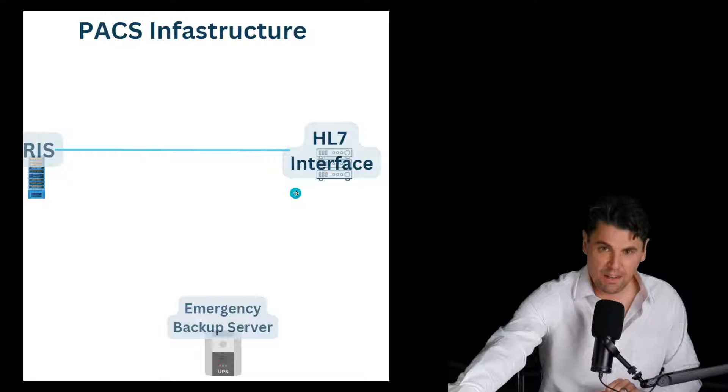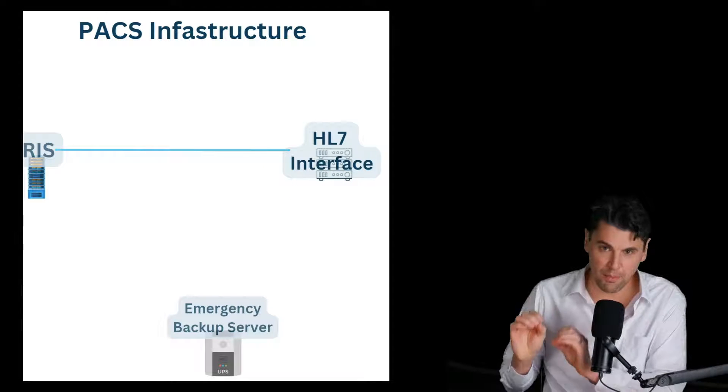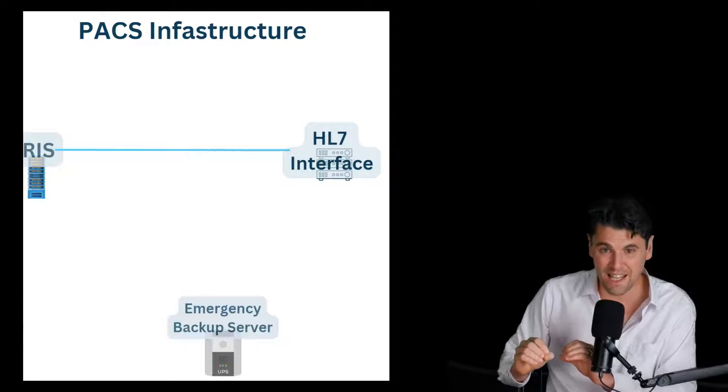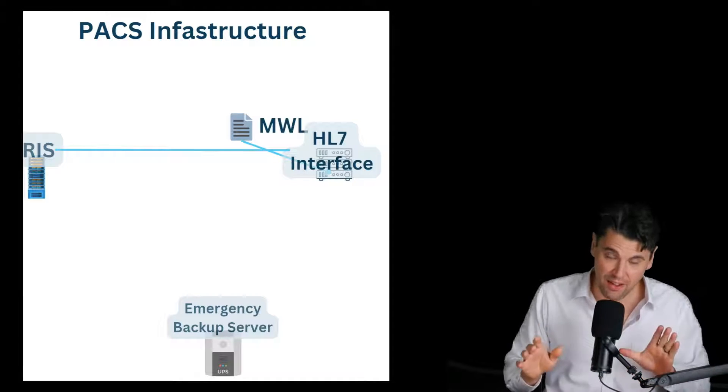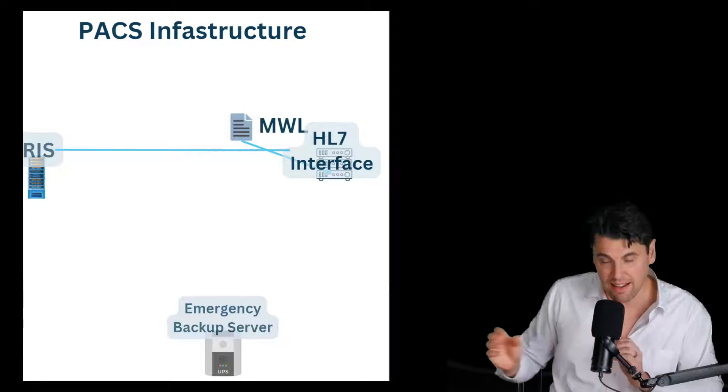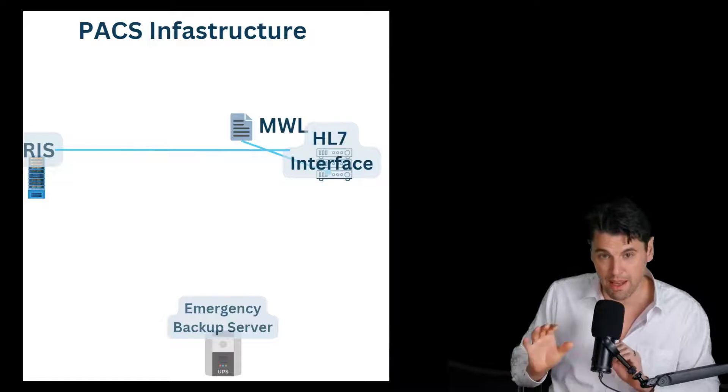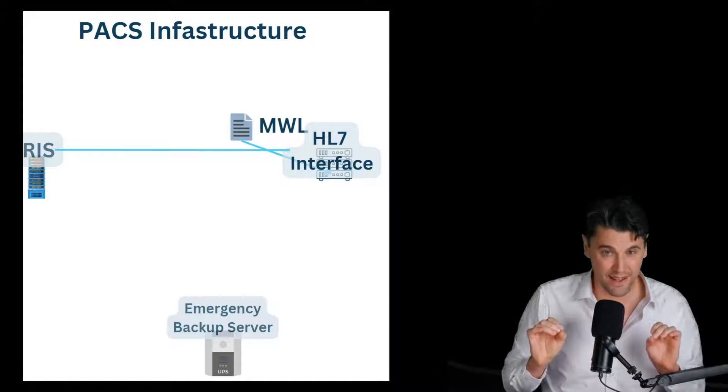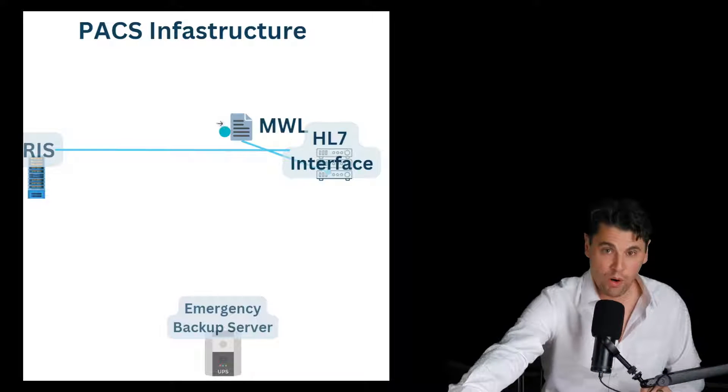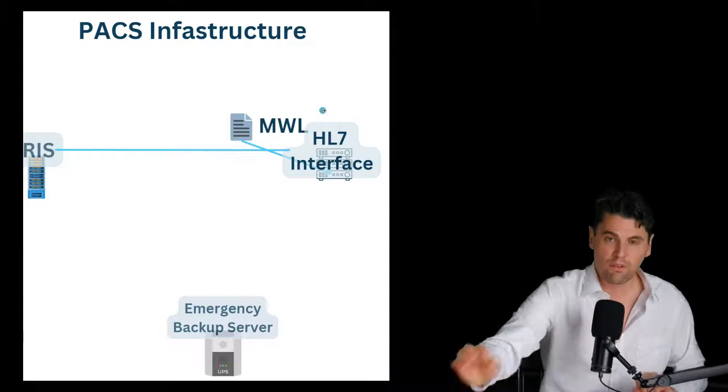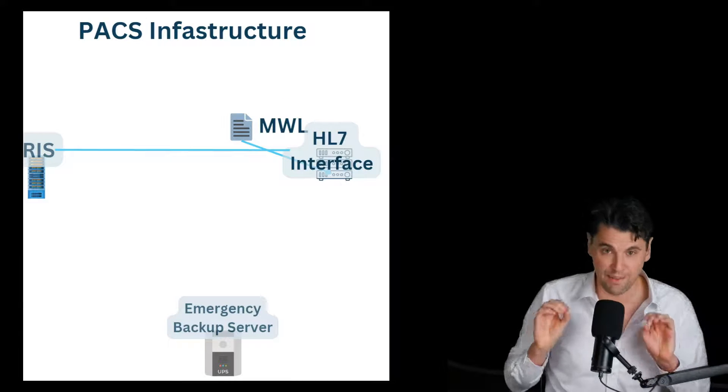So if we think about our radiology information system, the way that it communicates is actually with a certain type of interface called HL7 interface. HL7 is a standard for communicating these text-based requests within the medical system. Coming from the RIS, in the language of HL7, the modality work list is maintained, which keeps track of the different requests to be performed on different imaging modalities.